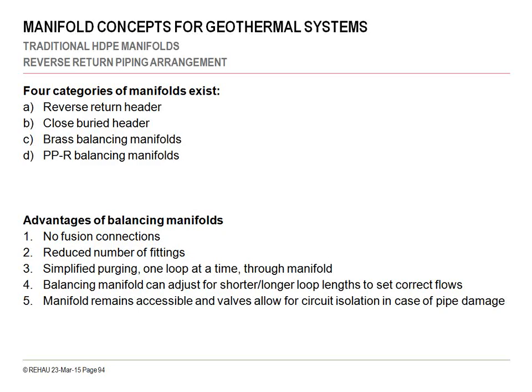In the case of commercial applications, just note we're controlling each borehole by having 2 branch tees at the tops of each borehole. And when you start your horizontal piping, we take those 2 supplies and 2 returns in each borehole, and with those branch tees, we'd have a 1-inch by 1-inch by 1.25-inch supply and a 1-inch by 1-inch by 1.25-inch return. So now you have a single supply and return coming from and going to each borehole back into the balancing manifolds, creating a circuit.